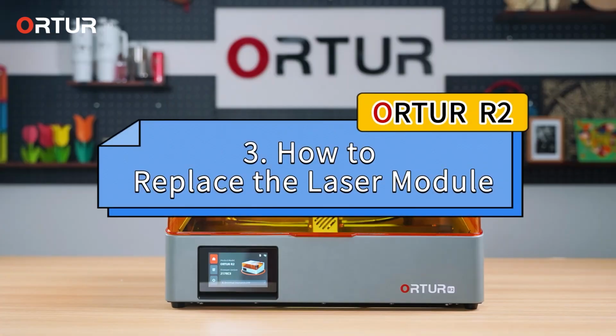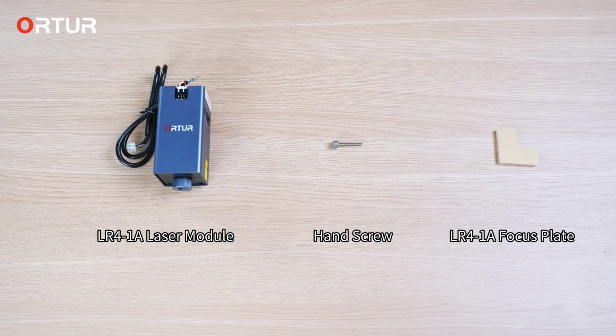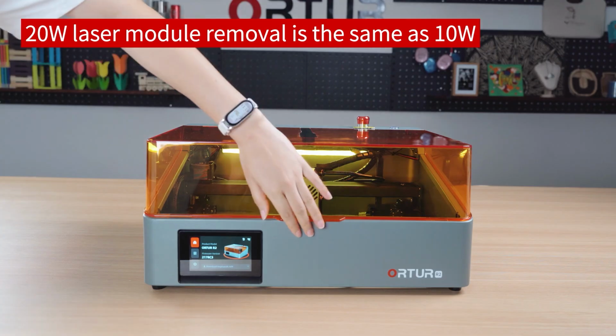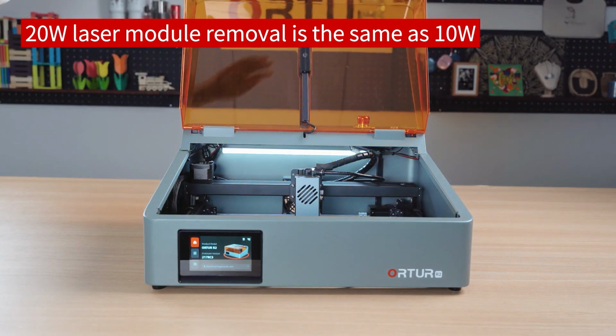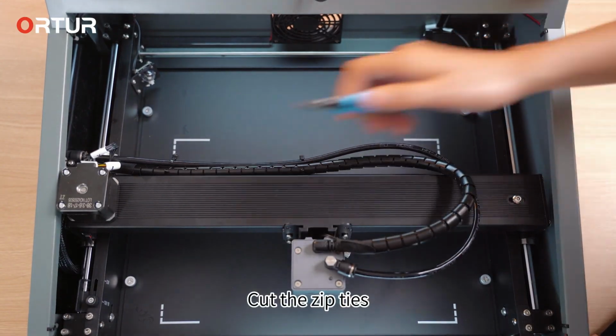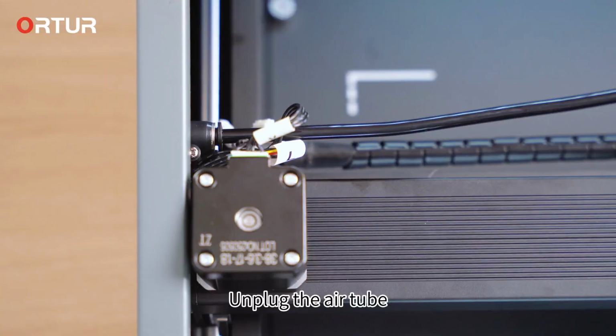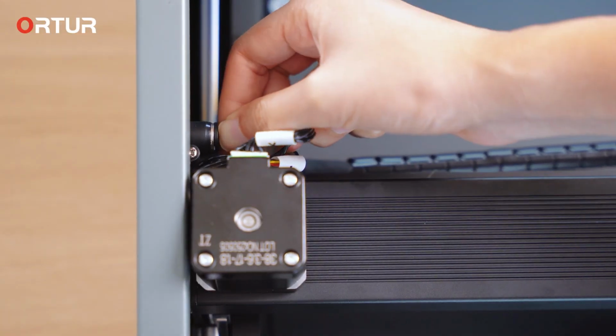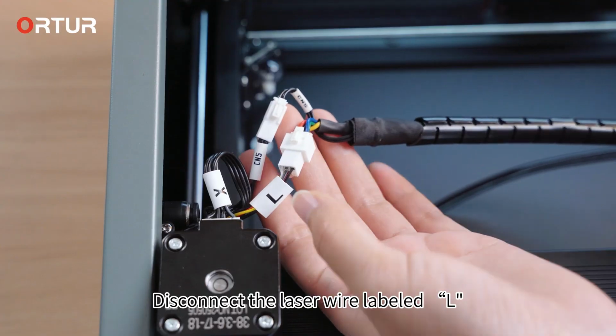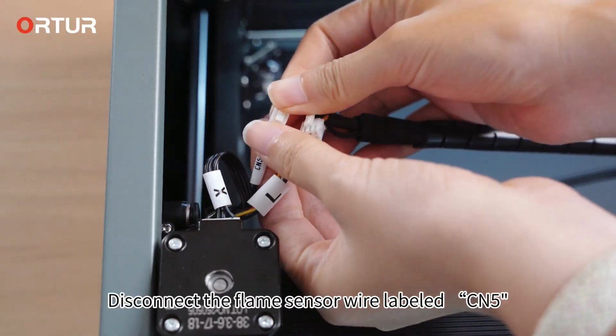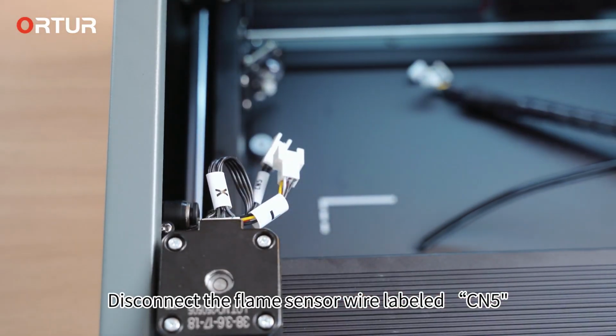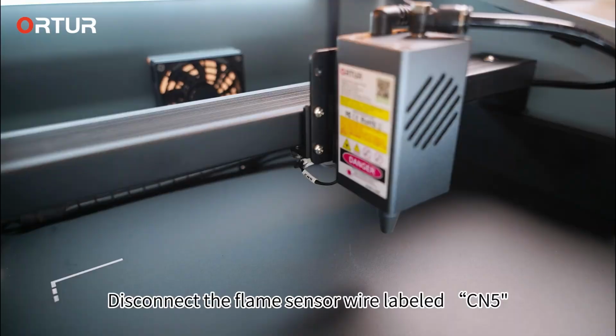3. How to replace the laser module. 20-watt laser module removal is the same as 10-watt. Cut the zip ties. Unplug the air tube. Disconnect the laser wire labeled L. Disconnect the flame sensor wire labeled CN5.